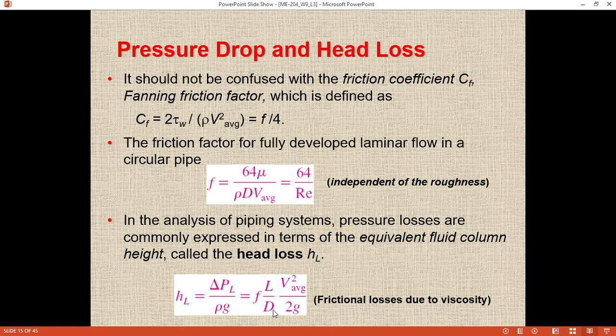So that is the friction loss due to viscosity. Once the pressure loss is known, the required pumping power to overcome the pressure drop can be determined. If you know the pressure drop, you can easily find the size of the pump or the motor required to push the water through that particular length of pipe. If you have a 100-meter length of pipe, how much pump power will you need to push the water through it? You can calculate that by using this formula. The work done by the pump for that particular length is equal to the volume flow rate.